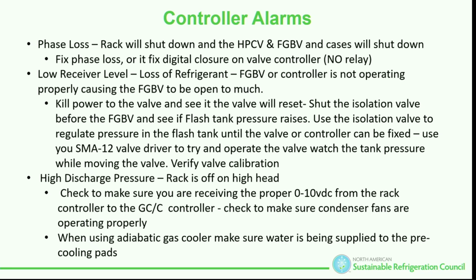Make sure they're clean. When you clean the pad, you also have to clean the little fitting, the little opening where the PVC comes up. We just recently found the PVC pipe broke. We couldn't understand why we were kicking on high head. They broke the PVC pipe and now the water is just pouring all over the pad. They had one little section of pad wet on the BAC. So we've got to look at these things. These things are there for a reason and do the right thing.